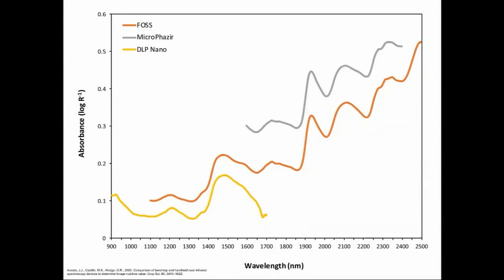But we can also see the differences in instrument response. So how much light were we able to get back in the instrument? In fact, I would expect that the smaller miniaturized instruments would have a harder time imaging the sample, but in this case you see that the microPHAZIR actually had more light captured by the instrument than the FOSS instrument. I would expect the FOSS instrument to be the benchmark here.